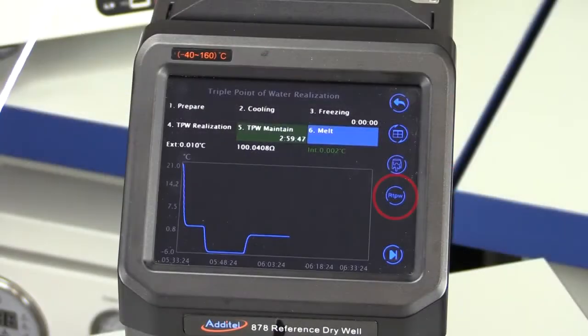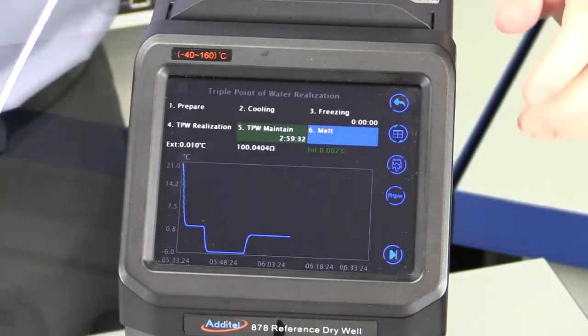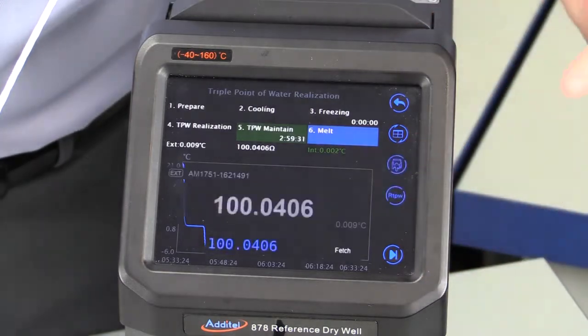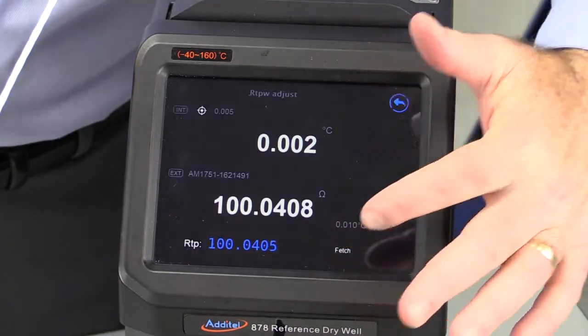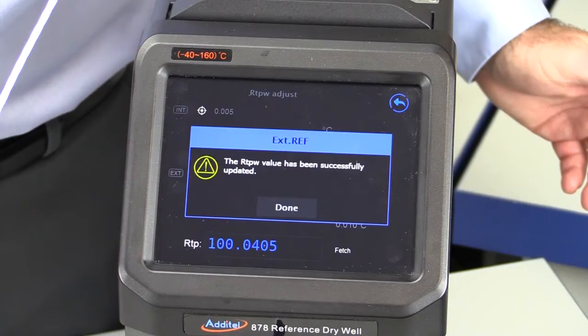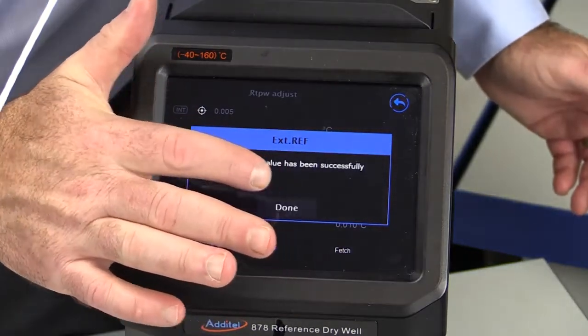When using a reference thermometer that's being read through the process option of the ADT878, we see that there is a triple point of water icon that illuminates after stabilization. If we select this icon, the RTPW function will allow you to automatically fetch and update the resistance at the triple point of water value in the smart connector of your reference thermometer.